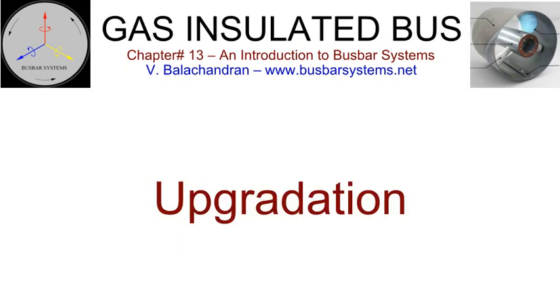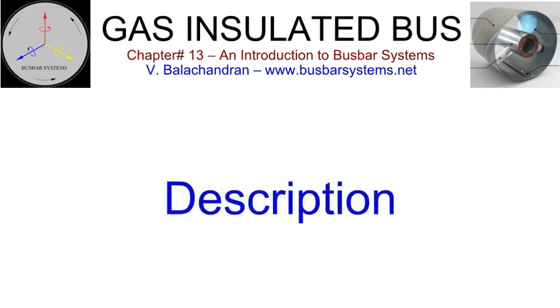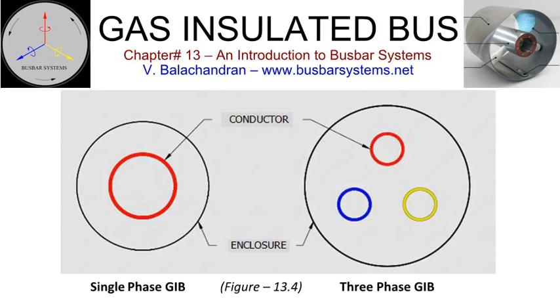Upgradation. Gas-insulated buses are also required when undertaking retrofitting, modification of an existing layout, and addition of bays to existing substations. It does offer a solution that would not have been possible with an air-insulated system. Description. The gas-insulated bus mainly comprises a cylindrical conductor or conductors located inside a cylindrical enclosure and supported by insulators. The annular space between the conductor and enclosure is filled with insulating gas. Sulfur hexafluoride. A mix of sulfur hexafluoride and nitrogen in the ratio of 20:80. Green gas for grid. There are 2 possible configurations for a GIB detailed below.